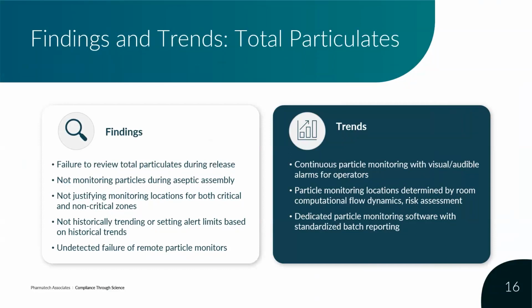Finally, in the past, what's happened is that the particle monitors that were being added to a facility were in fact being integrated with things like BMS systems that were not specifically designed for particle monitoring, particularly in how they dealt with the data and actually triggered the alarms and in fact generated batch reports. So we're seeing really the trend of using this specifically designed particle monitoring system that has very specific software with very good batch reporting so that you get a very easy to read and easy to understand report on lot release so that the quality professionals can assess that in fact the particle limits had not been exceeded.